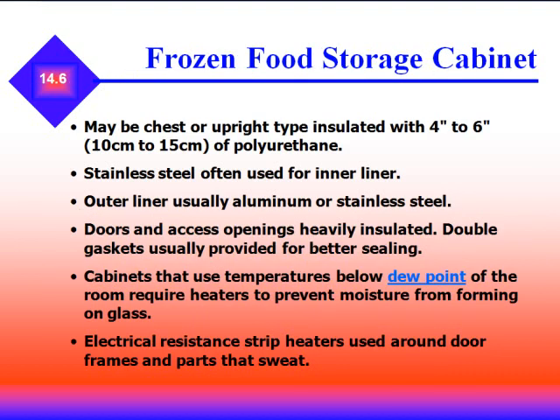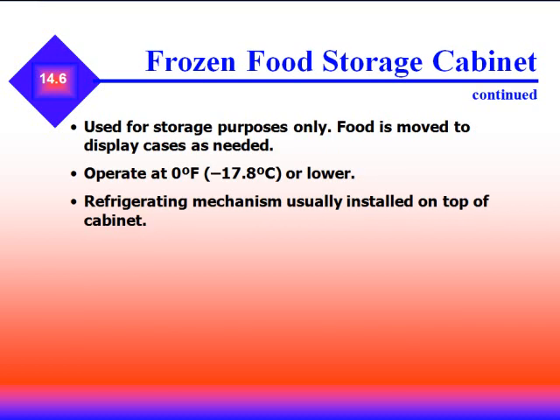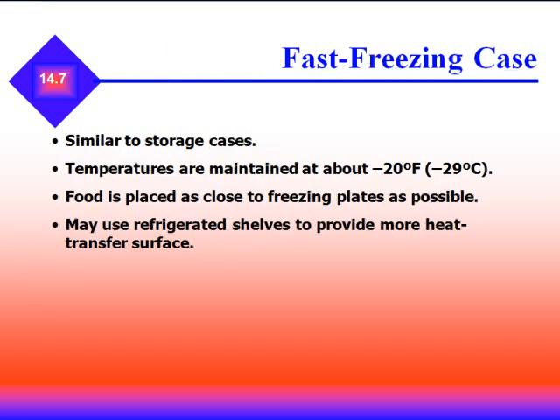The frozen food storage cabinet is frequently seen in grocery stores. It is a chest or upright type insulated with 4 to 6 inches of polyurethane, with stainless steel inner liner and aluminum or stainless steel outer liner. Doors and access openings are heavily insulated with double gaskets for better sealing. Electrical resistance strip heaters are used around door frames to prevent moisture forming on the glass. These cabinets operate at zero degrees or lower, with the refrigerating mechanism usually installed at the top. The fast freezing case maintains temperatures at about negative 20°F and may use refrigerated shelves to provide more heat transfer surface.